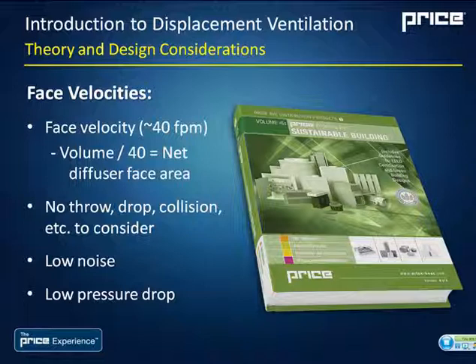There's nothing to consider like throw or drop or collision of diffuser air streams. The layout is actually really simple, and as you may have seen from the smoke video, the air just travels around the room. It kind of trickles along the floor and seeks out the heat sources. So furniture and strange geometry rooms aren't really much of a concern.